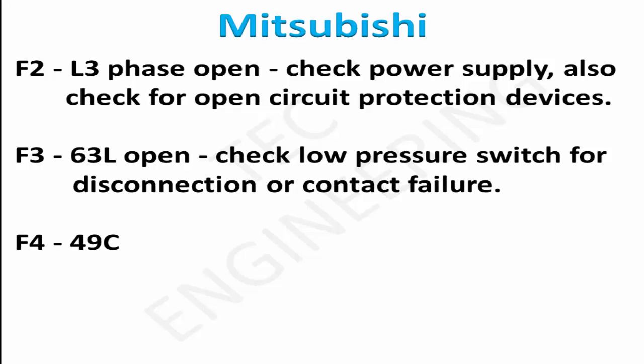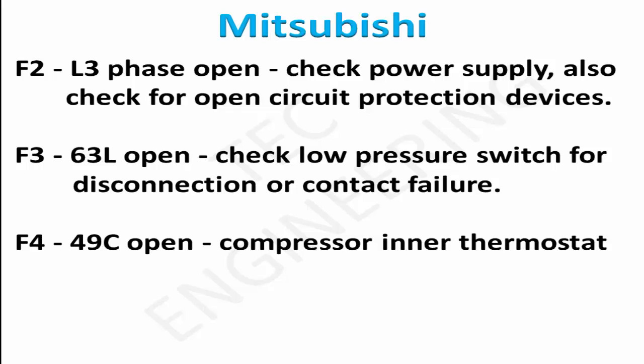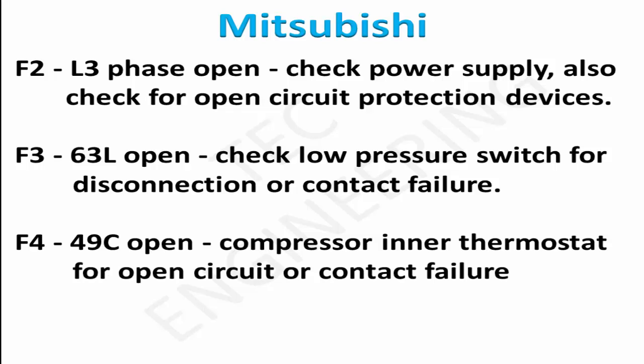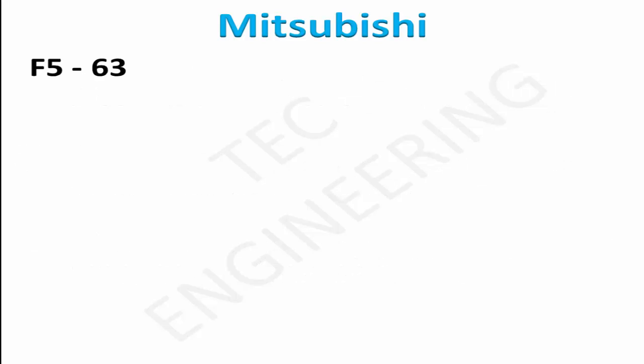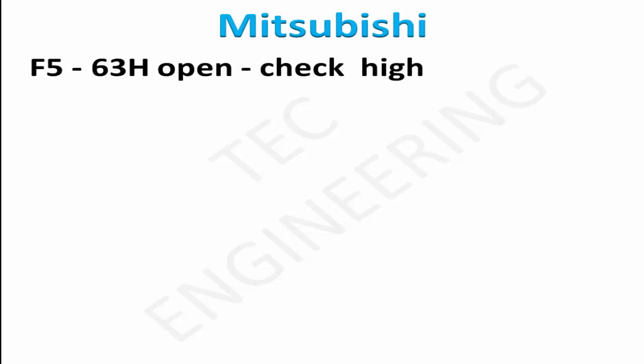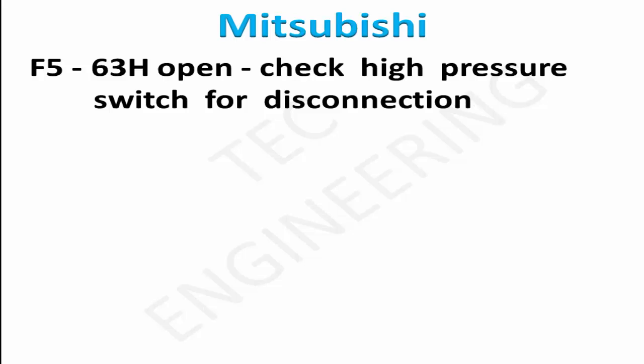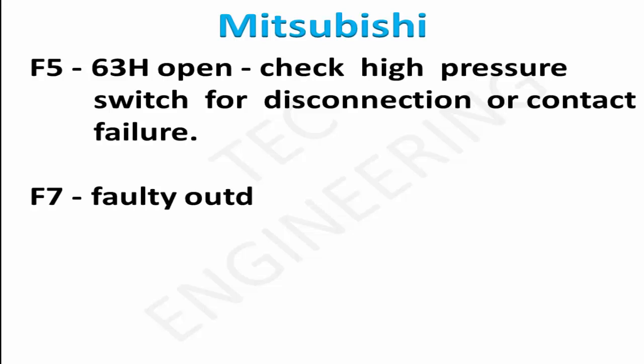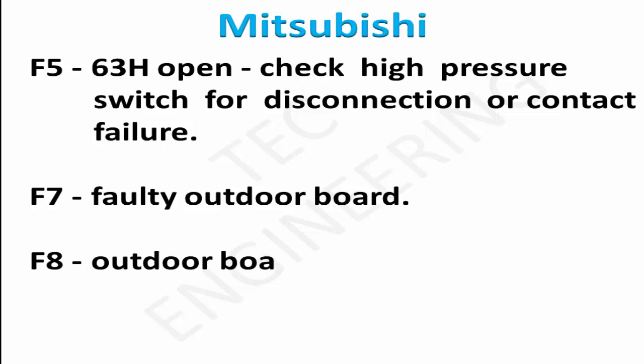F4: 49C open — check compressor inner thermostat for open circuit or contact failure. F5: 63H open — check high pressure switch for disconnection or contact failure. F7: faulty outdoor board. F8: outdoor board defective.